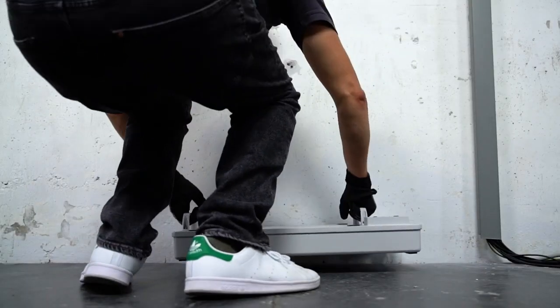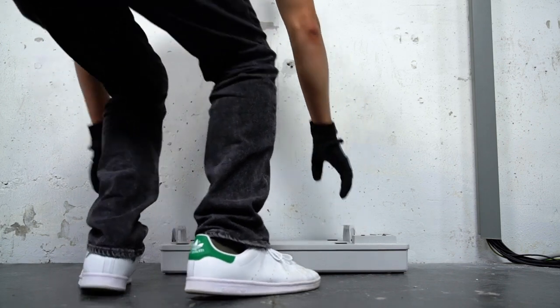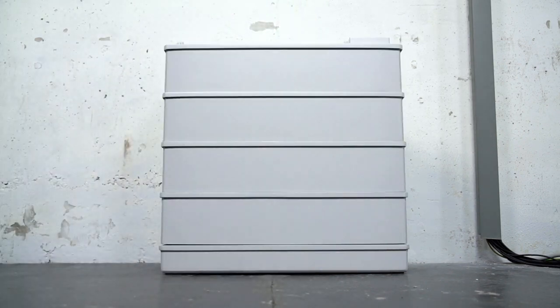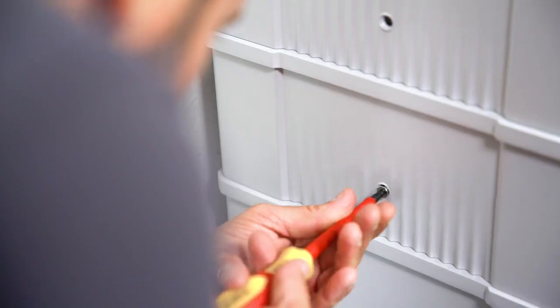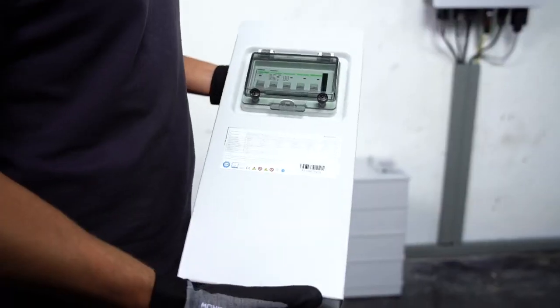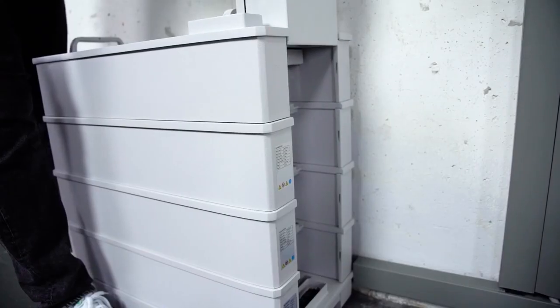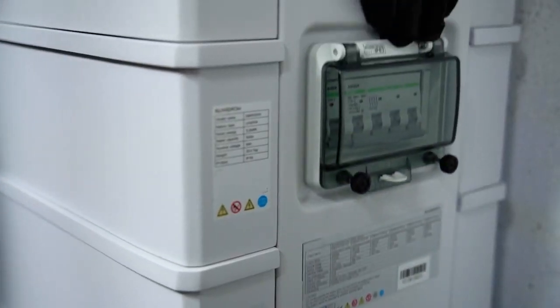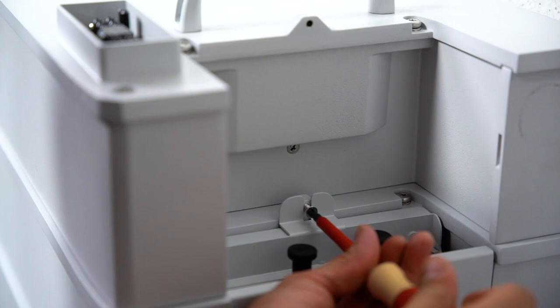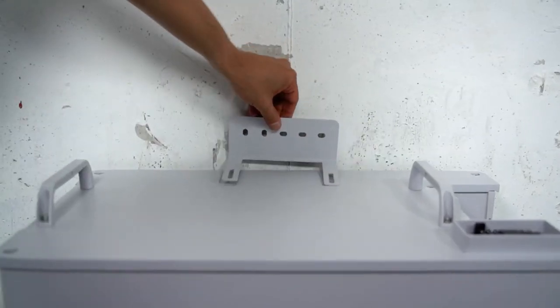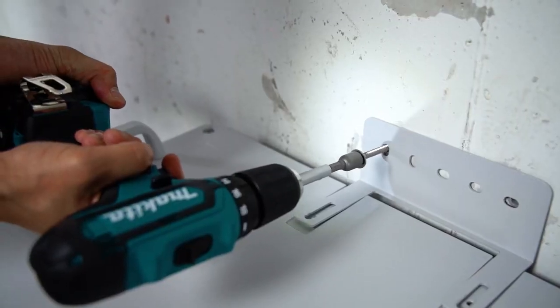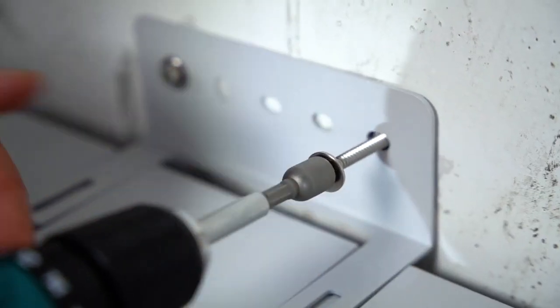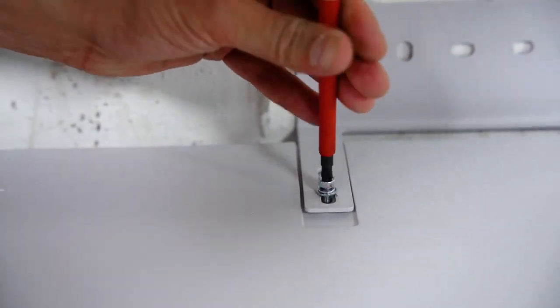Pay attention to leaving enough space between wall and battery. This is mandatory as the cabling will come out at the back of the battery in the end. With 33 kilograms, the individual modules are easy to handle. They are designed to be installed in a simple plug-and-play style. Fix the modules on both sides with the included M5 screws. Next step is to connect the switchgear to the base. Slide it into the foreseen slot on the right side of the battery and fix it with the included M5 screw. Once all modules and the switchgear are in place, it's time to fix the battery on the wall. You'll need the included M4 screws for the wall and M5 screws for the module.